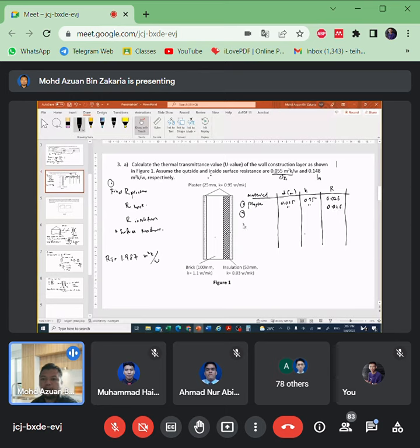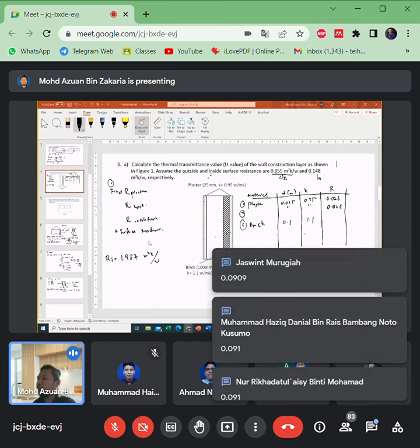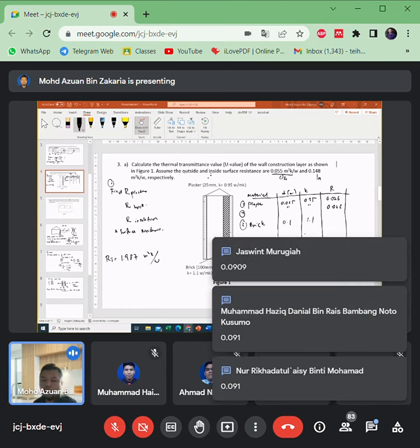0.026. And then number 3, we have brick. Brick is 0.1 divided by 1.1. So what is the R value for brick? Okay, 0.091.